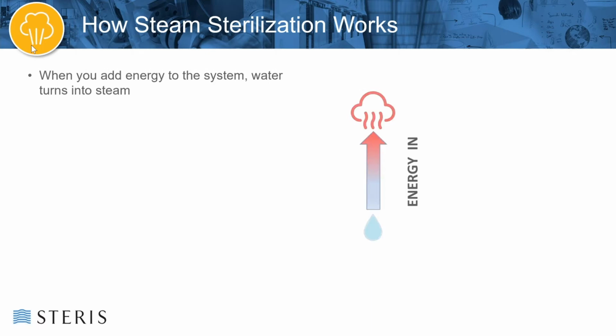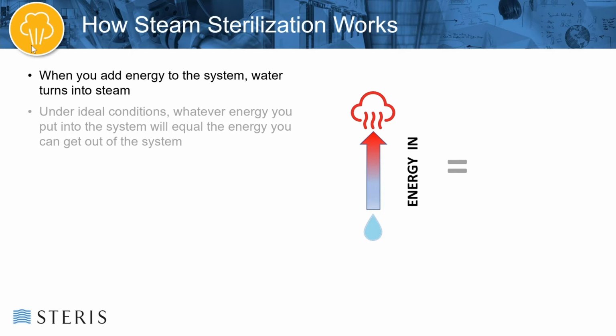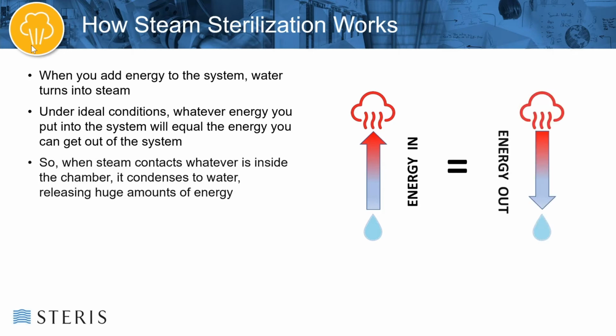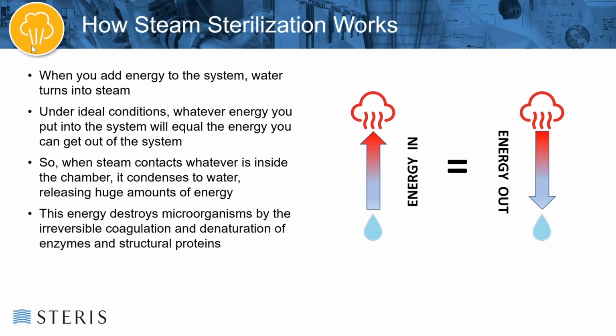So let's talk a little bit about how steam sterilization works. Basically, when you add energy to the system, you're going to turn water into steam. This is what takes place in the steam generator or the boiler. You're adding energy into the system, you're turning water into steam, and that steam will contain a lot of energy. Now, under ideal conditions, whatever energy you put into a system, you'll get that same amount of energy out of the system. So as steam is injected into the chamber and contacts whatever is inside the chamber, it condenses to water, which releases a huge amount of energy. And it's this energy that effectively destroys microorganisms by the irreversible coagulation and denaturation of enzymes and structural proteins.